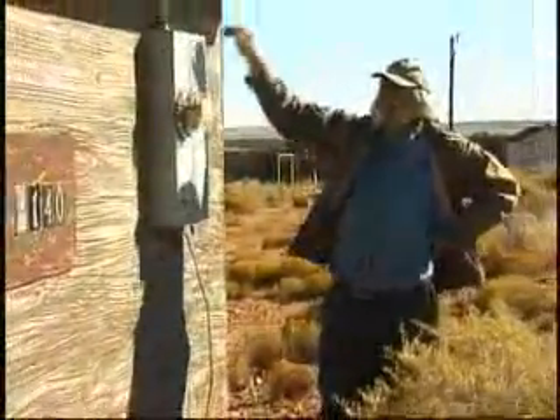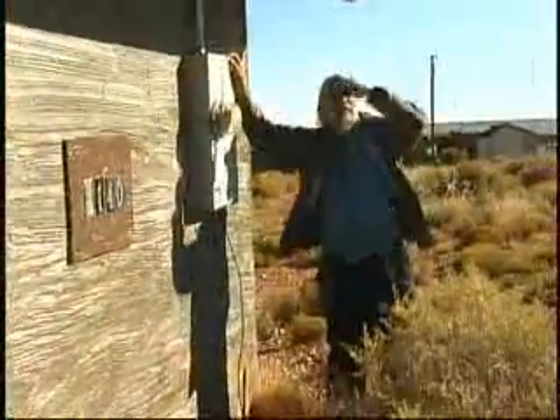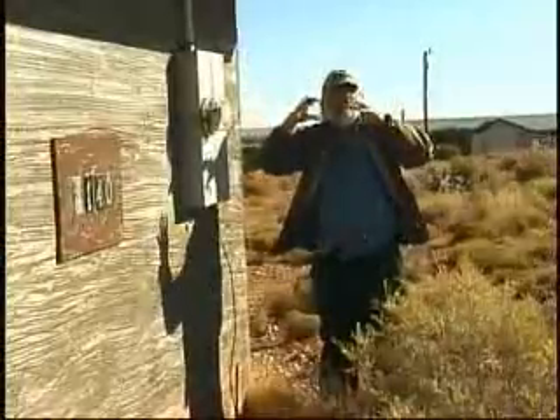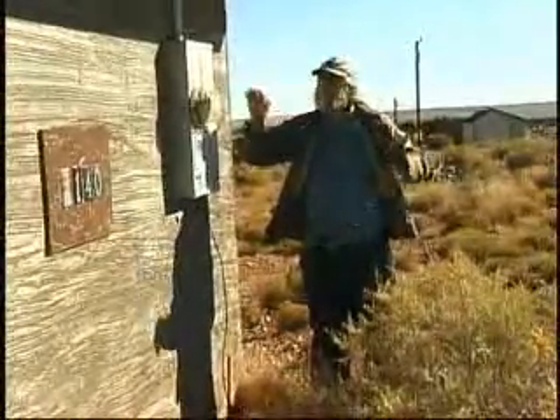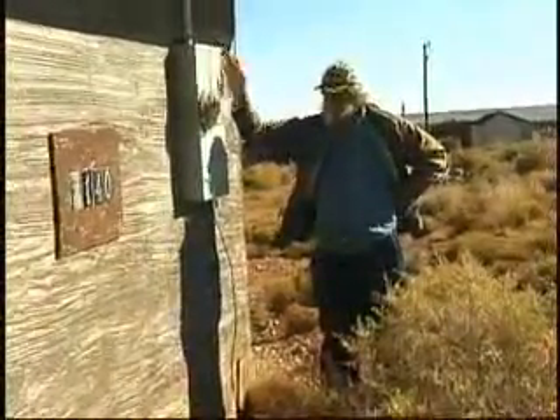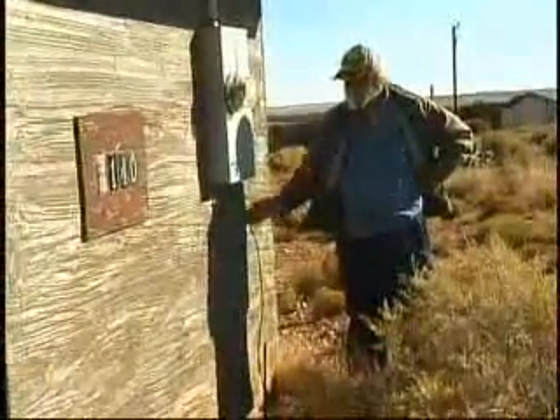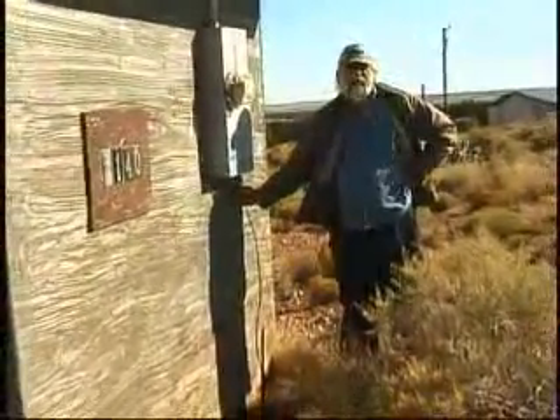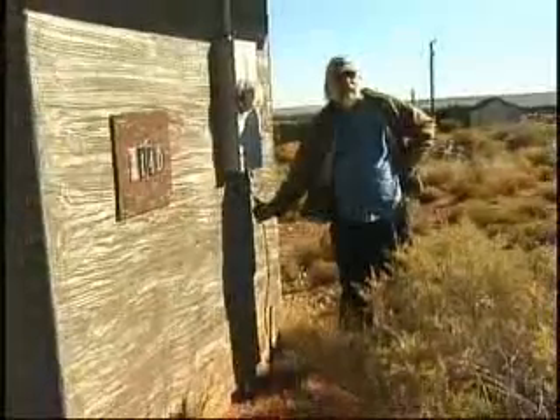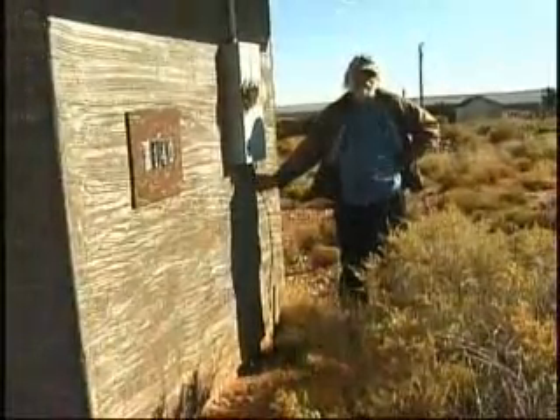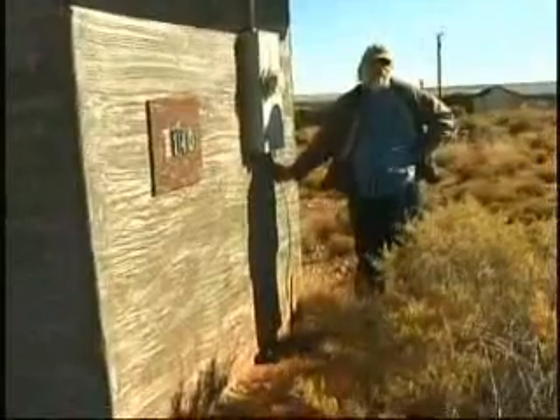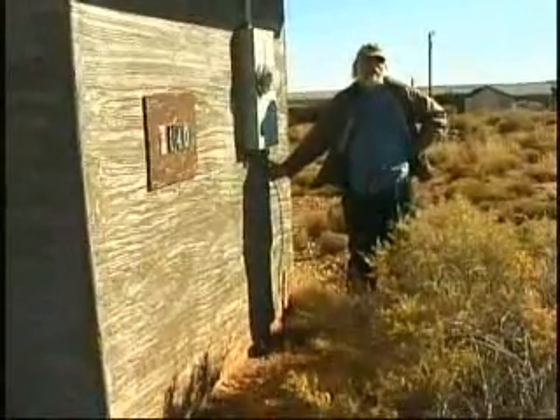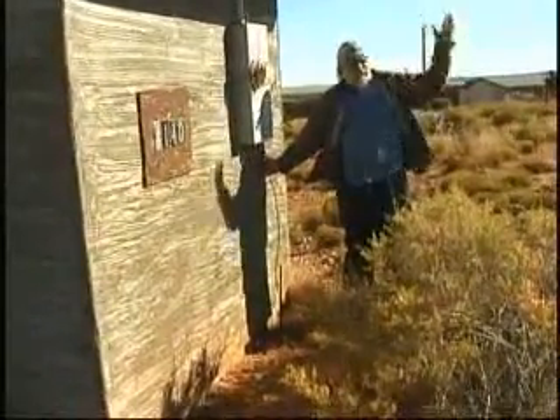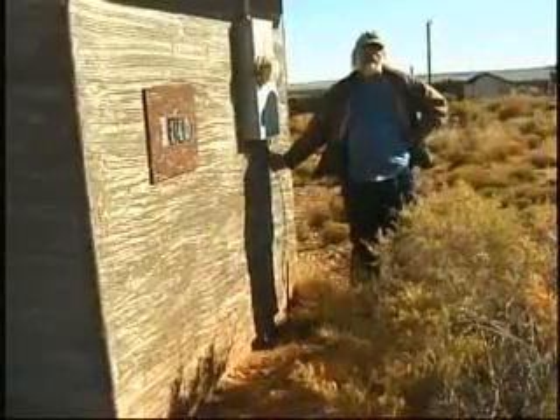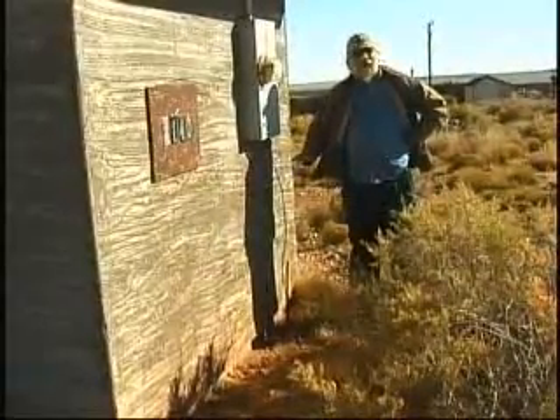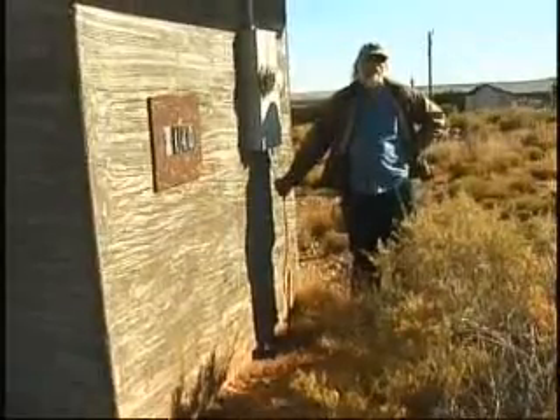Think of it like a fusible link, the thing that breaks first. A lot of times, and I'm guilty of this myself, we don't have a ground wire larger than the wires going into the building. So if a truly energetic surge came down the wires, it would take out the smallest wire first, and in a lot of cases that's the ground wire.